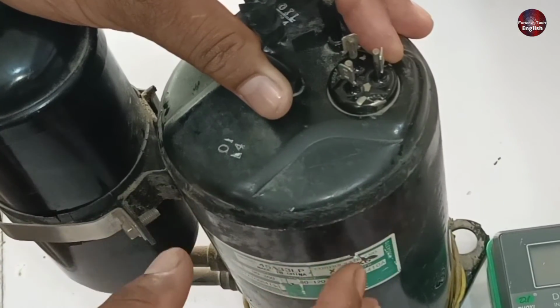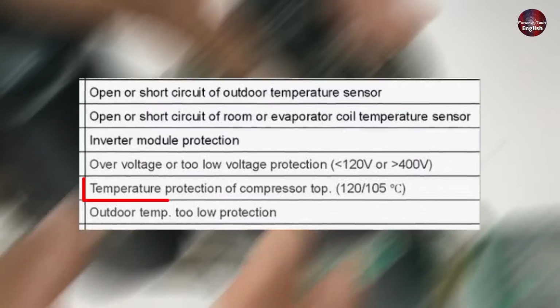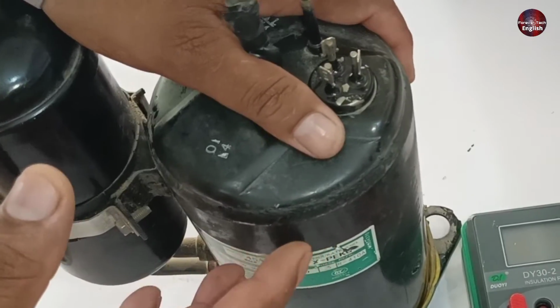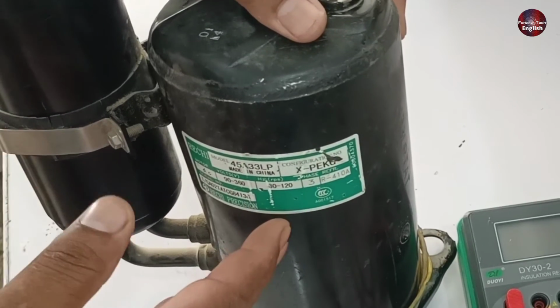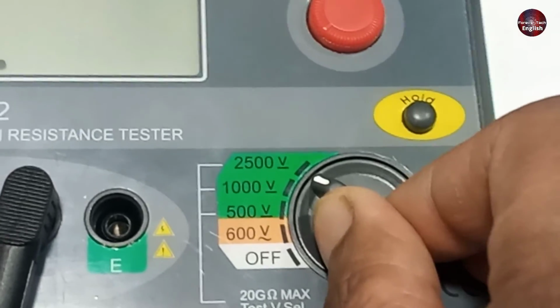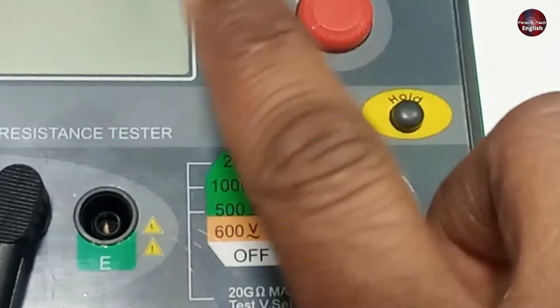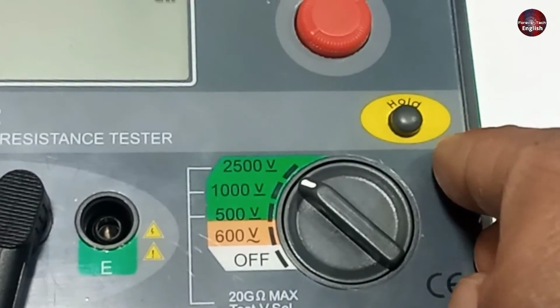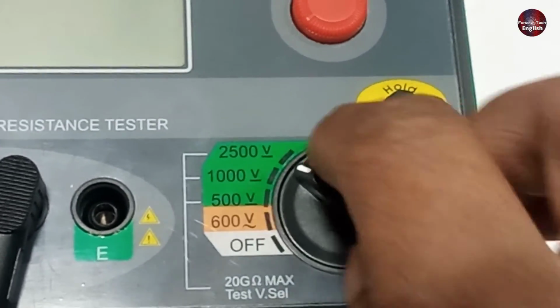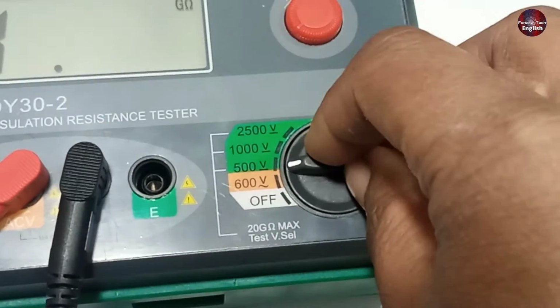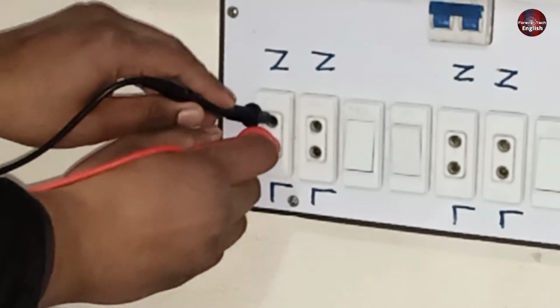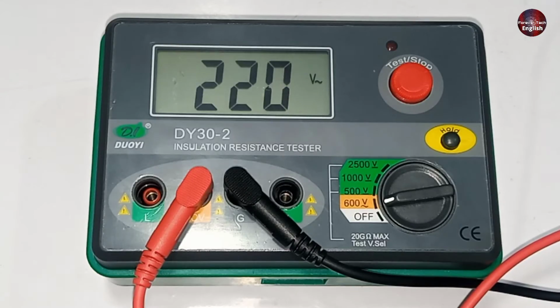And when more voltage flows towards these compressors, the PCB shows over voltage protection. So always test the compressor at a maximum of 1000 volts. Never test on 2500 volts, as these are very high voltages. As the chances of the small compressor getting damaged are high. And on the AC mode, it can check a maximum of 600 normal AC electricity. Don't test high voltages with this tester as it will damage the tester or could be dangerous.